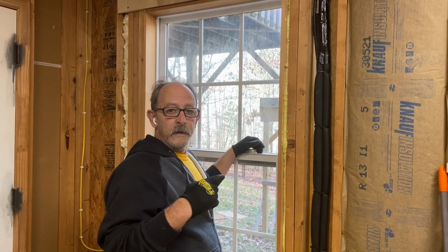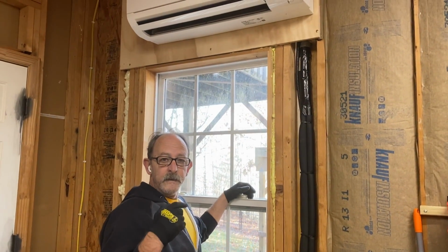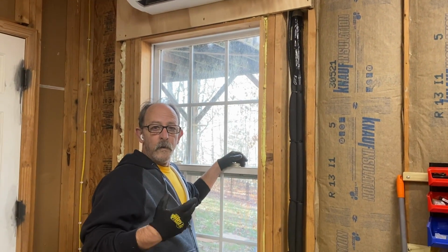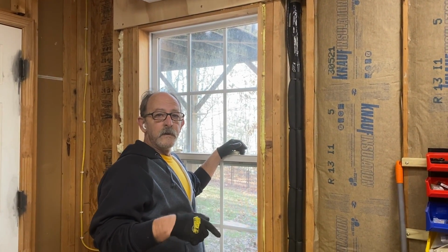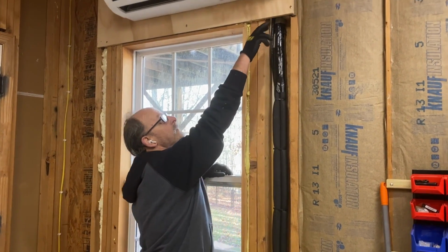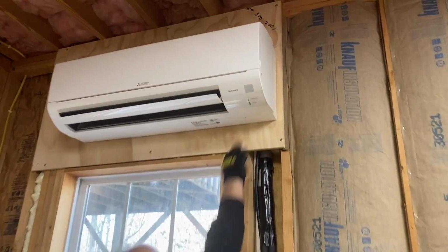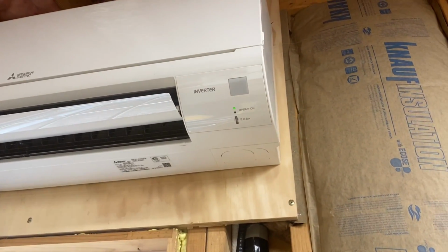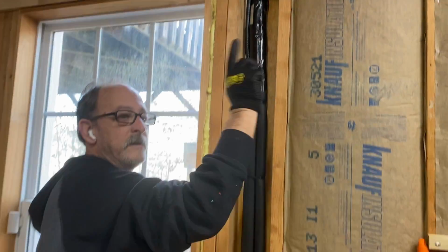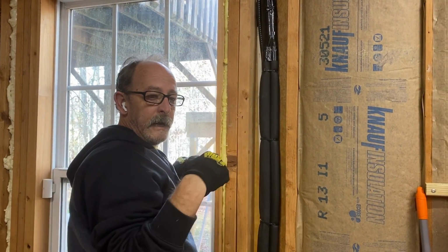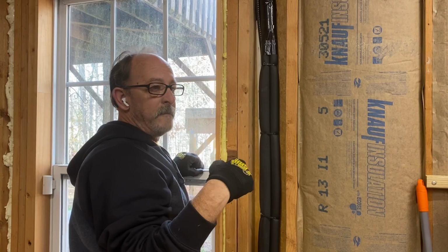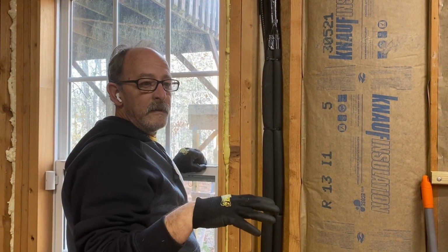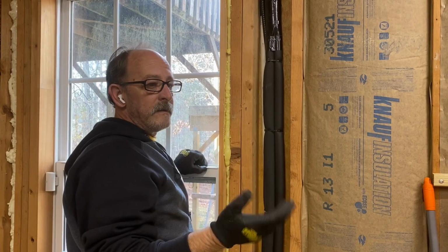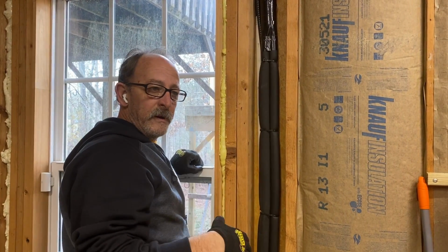If we want to put our unit into emergency operation so we can test the compressor and do what we call an inverter test, all we have to do is come inside and find the E/O switch right here. To put it in cooling, we would push it in one time. To put it in heating, we would push it in 2 times. But in this case, we're just going to test it in cooling because all I care about is to see if the board is good or the compressor is good.